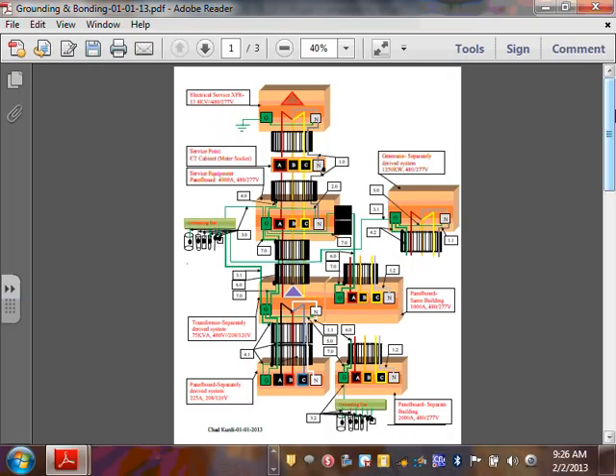So that's my service. From my service, I'm going to give you the big picture. I took a feeder and fed a transformer. This will be a 480 delta-Y transformer. And from that transformer, I derived the neutral, the white neutral, and fed a 208/120 panel. Typical in every commercial building, guys, you want to have two voltages, right? 480/277 and 208/120. That's the separately derived system, the transformer separately derived system. So I took a feeder and fed this transformer. From the transformer, I fed typically a 225 amp panel, 300 amp panel, a receptacle panel. Cool? So that's a feeder coming through the transformer.